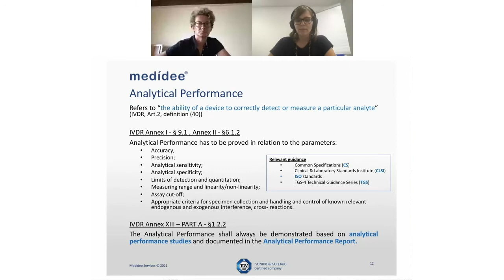Coming back to the same table illustrated before, the analytical performance of the device needs to be equally addressed, whether it is an established and standardized test, a non-standardized test, or a new test. And it also does not depend specifically on the IVD classification. So analytical performance is also something that needs to be demonstrated for all devices.